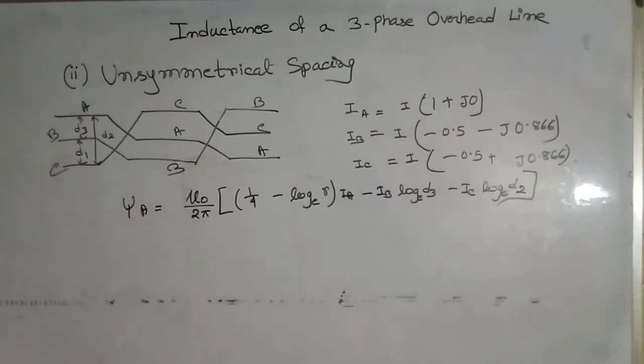Now we generally interchange the position of the conductors at regular intervals along the line so that each conductor occupies the original position of every other conductor over an equal distance. Such exchange of position is known as transposition. I will discuss transposition in detail in the presentation.